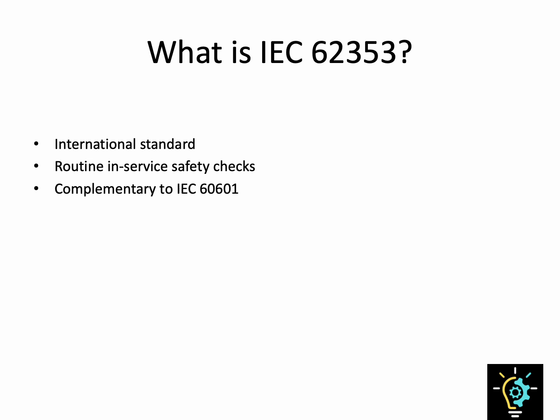One of its key innovations is how it addresses dielectric integrity through two main leakage tests: equipment leakage, which looks at the total leakage from the mains into the equipment, confirming the means of operator protection, otherwise called MOOP, and applied part leakage, which ensures that the floating applied parts, think of BF and CF type connections, remain at safe levels, confirming the means of patient protection, MOPP. These tests help confirm that the safety barriers inside the device are still intact after they've left the factory. IEC 62353 adapts to this. It gives us field service engineers tools that work in real-world environments, not lab conditions, without compromising safety.